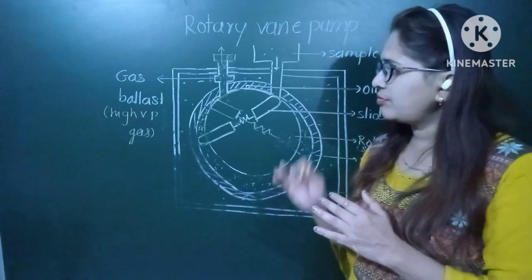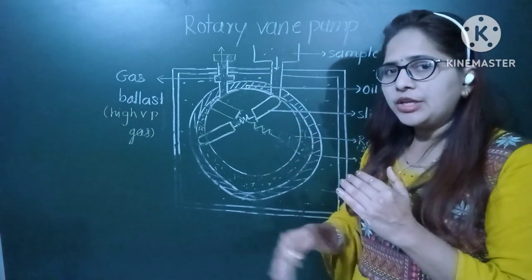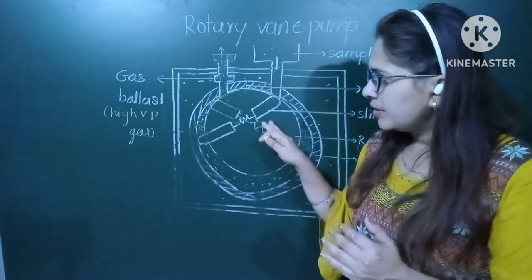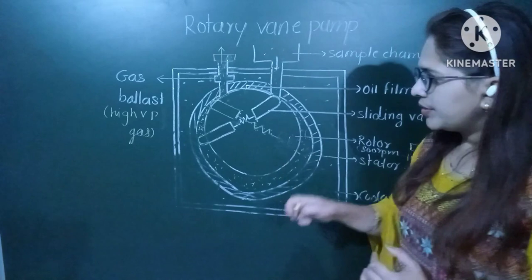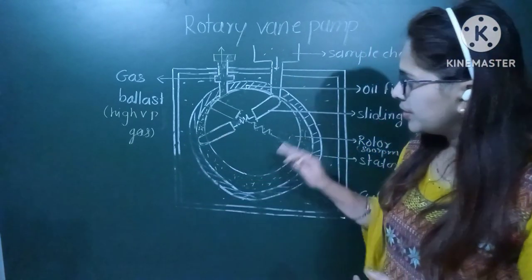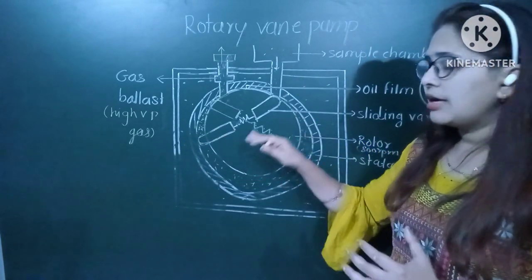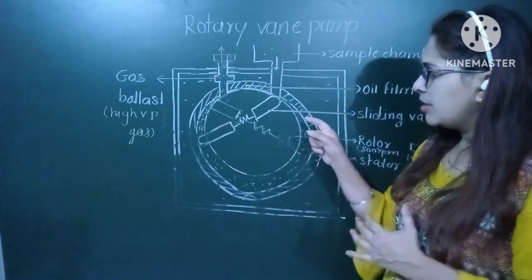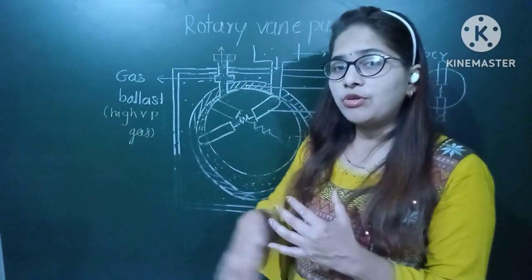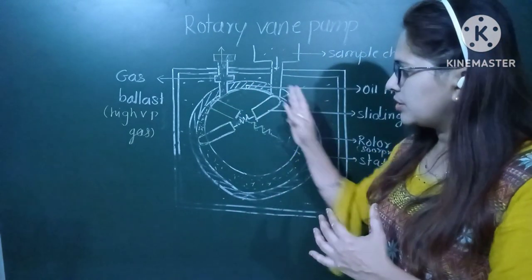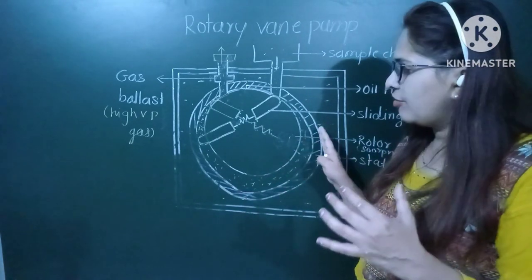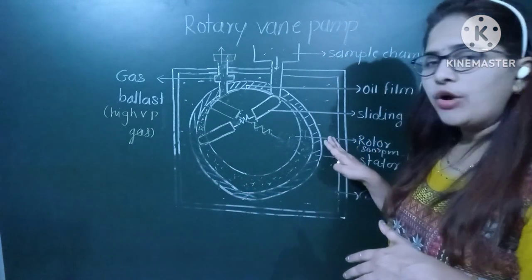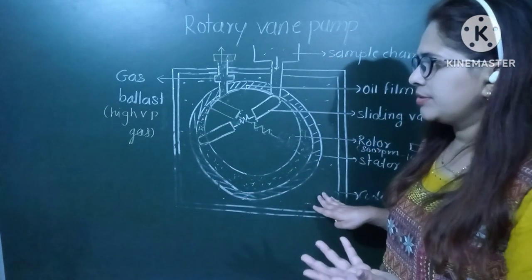With the help of this rotary pump, we can remove the air molecules continuously from the sample chamber. As the rotor is moving at very high speed — nearly 800 to 1400 RPMs — a large amount of heat is generated. There is a possibility of heating of the stator. Therefore, the whole arrangement is kept in oil or a coolant.